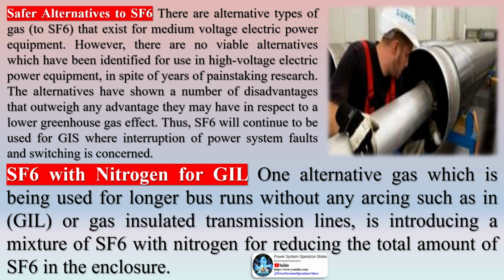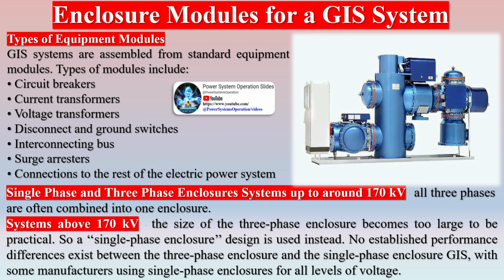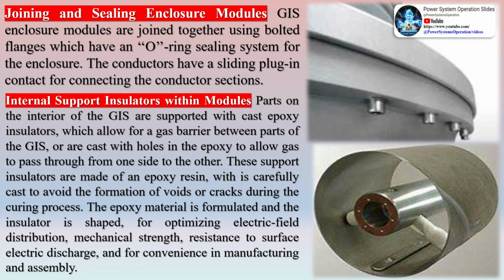However, there are no viable alternatives which have been identified for use in high voltage electric power equipment, in spite of years of painstaking research. The alternatives have shown a number of disadvantages that outweigh any advantage they may have in respect to a lower greenhouse gas effect. Thus, SF6 will continue to be used for GIS where interruption of power system faults and switching is concerned. GIS systems are assembled from standard equipment modules. Types of modules include circuit breakers, current transformers, voltage transformers, disconnect and ground switches, interconnecting bus, surge arresters, connections to the rest of the electric power system.